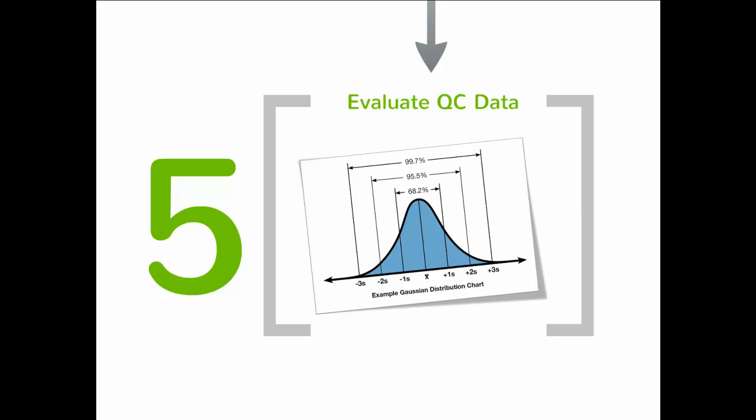QC data greater than 2s but within the 3s limit does not necessarily indicate that the run must be rejected, as approximately 4% of the valid data points will fall between 2s and 3s.